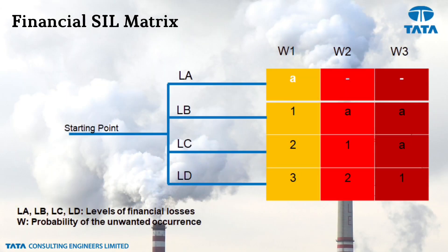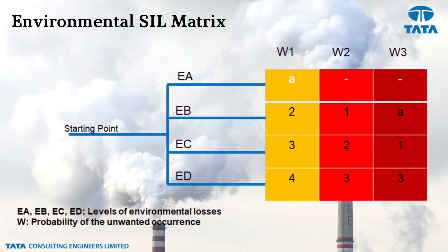Similarly, financial SIL is determined using parameters LA, LB, LC, and LD representing levels of financial losses. Environmental SIL is also determined using its own matrix. For each loop, safety SIL, financial SIL, and environmental SIL are all determined, and the highest among the three is taken as the final SIL rating for that loop.